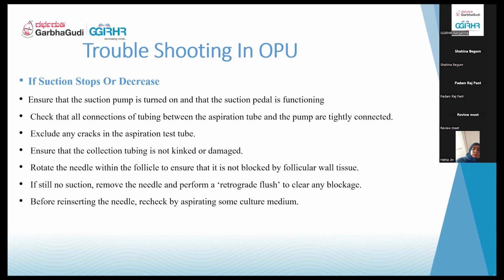This is where we tell you to do a little curettage, because sometimes the follicular wall gets stuck onto the needle tip. Because it is stuck onto it, you're not able to provide proper aspiration pressure for the rest of the follicular fluid. You just do a little curettage, then it gets released, and then the aspiration takes place. If still no suction, then remove the needle and perform a retrograde flush to clear any blockage.